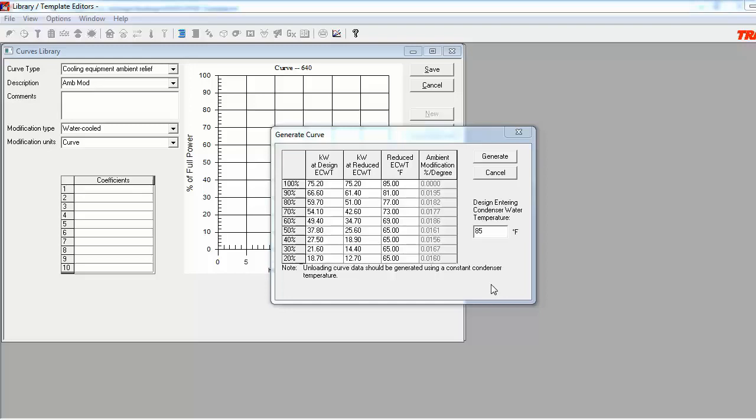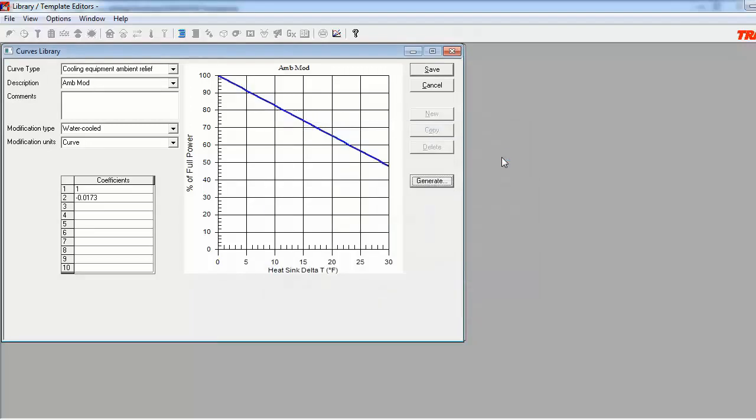With this completed, I can click on the Generate button, and the program will plot out the graph for the Ambient Modification curve. As you can see, the curve has a backwards declining slope to it, and the curve coefficients are 1 and negative 0.0173. The negative second coefficient is an average of the Ambient Modification Percent Degree column values. That does it for the Ambient Modification curve. Now I can go ahead and click on Save.